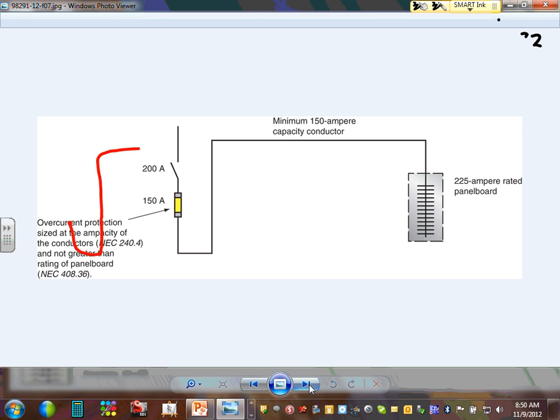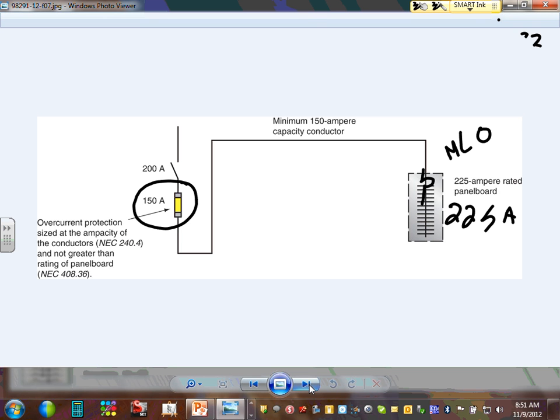Panels. When you have a panel, you can have the overcurrent protection device inside the panel. This is a 225 amp panel. This is called main lugs only. Do you remember main lugs only? Why do they call it main lugs only? Because the overcurrent protection device is ahead of it, somewhere else. Now, I don't know how many of you guys know that. Probably you, because you're journeymen. Anybody tell me what's the advantage of doing it this way versus putting it right in here, 150? It has to do with safety. What's the advantage of putting it here versus putting it here?